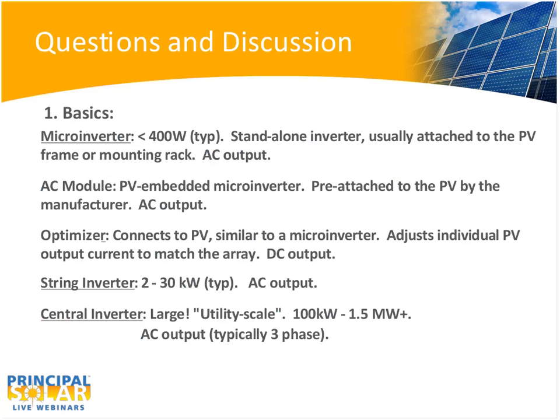Microinverters are typically a 400-watt maximum small inverter, and it is a standalone inverter. However, they are usually attached to the photovoltaic module frame or mounting rack. They can, if you wanted to be silly enough, be mounted 100 feet away, and as long as you run code-compliant wiring and everything else, there's nothing to prevent you from attaching 10 or 20 microinverters on the wall, let's say in your garage or elsewhere. Do they do it? No. It's a matter of economics and common sense.